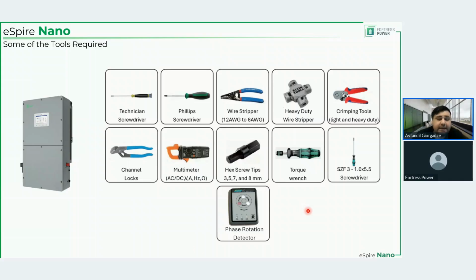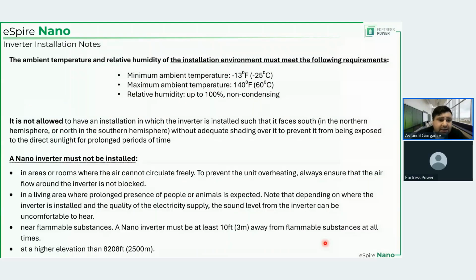Right? Now, a couple of notes about the inverter installation. And again, we're talking about the inverters themselves, not the inverter plus battery. The ambient temperature and relative humidity of the installation environment must meet these requirements. So ambient temperature should never be less than minus 25 degrees Celsius or minus 13 degrees Fahrenheit.